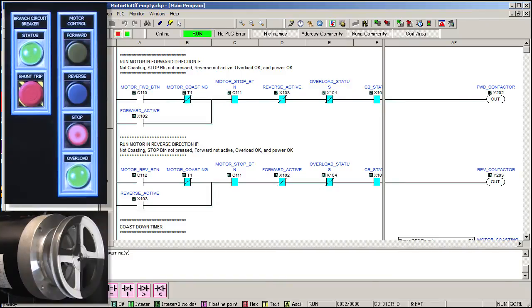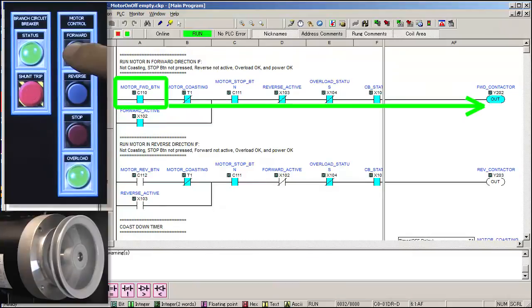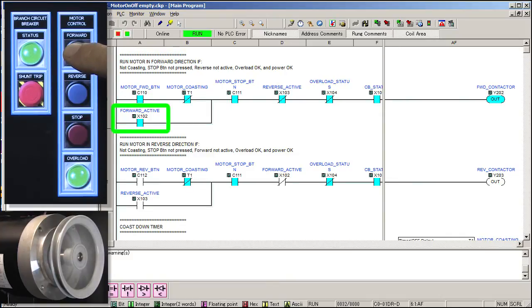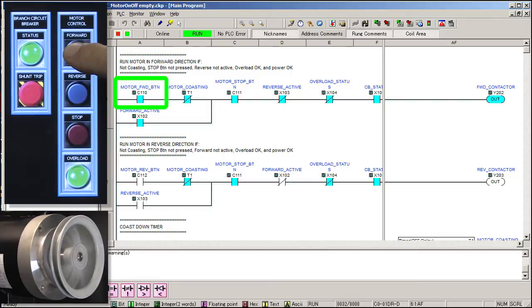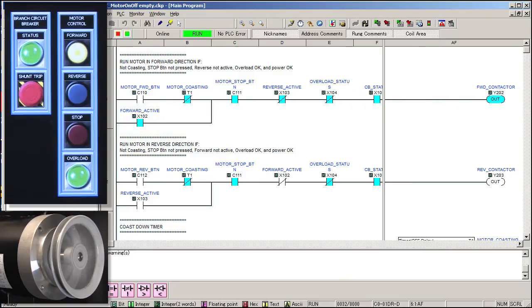So, when we press the forward button, we now have all the contacts on this rung active and power flows to the output coil and starts the motor spinning. Once the contactor engages, its AUX contact will also engage, which is this contact right here. So, when we release the momentary forward button, this AUX contact will keep the motor running. We call that sealing or latching the circuit.